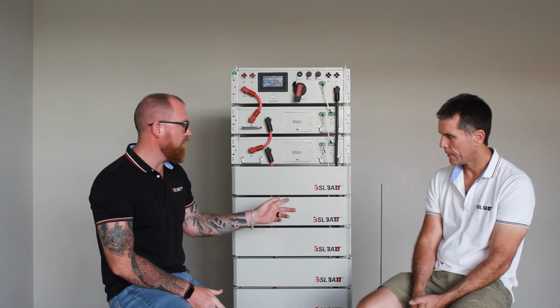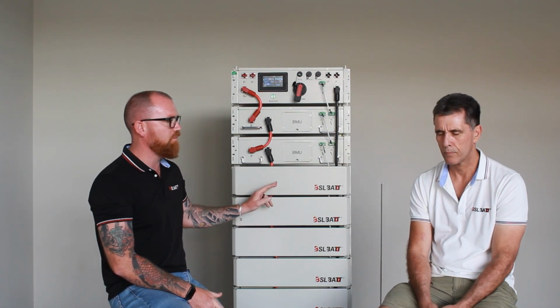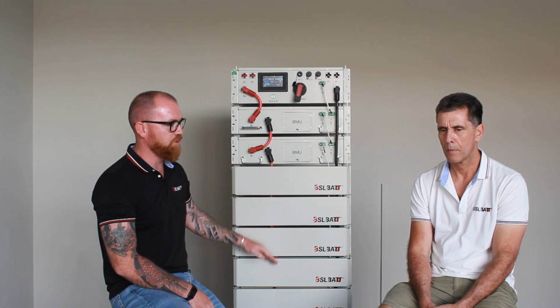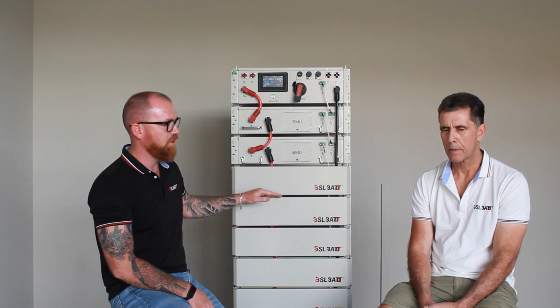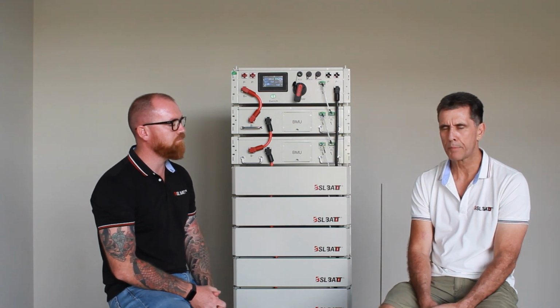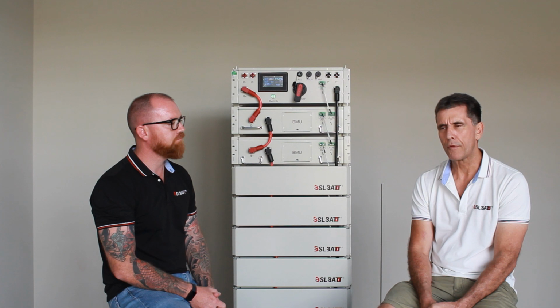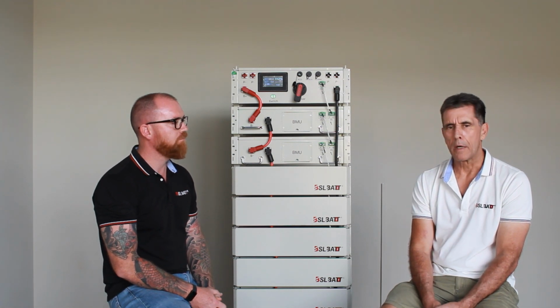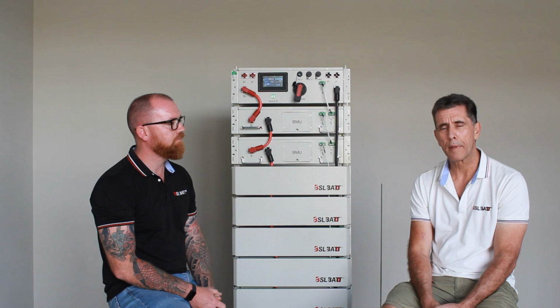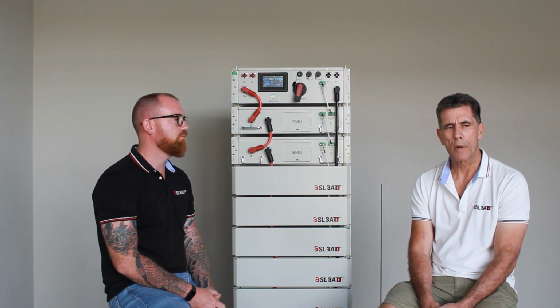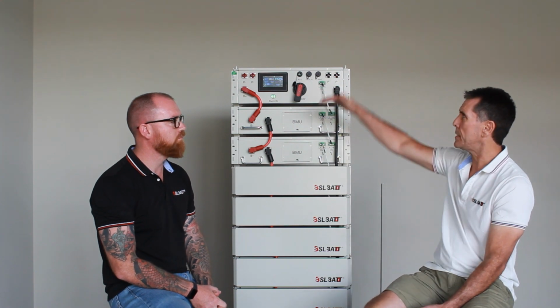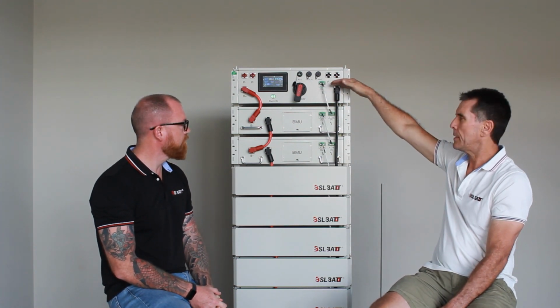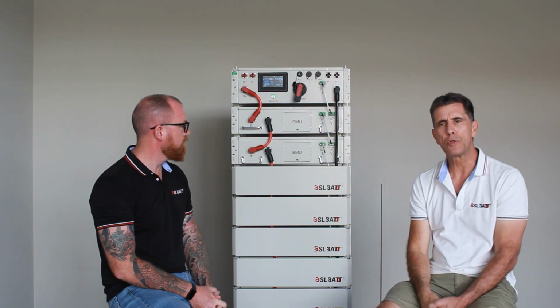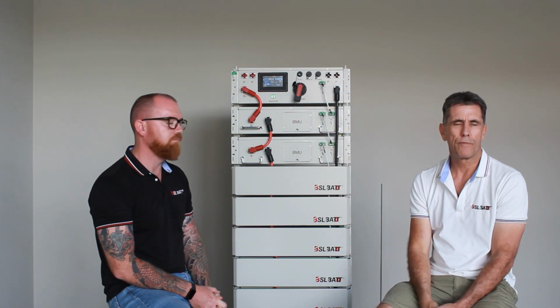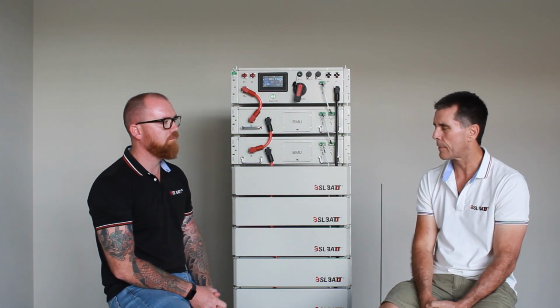In terms of this battery, we mentioned in our first video that it's a 7.7 kilowatt module, each module, with built-in fire suppression - about 7.8, just shy of 7.8 kilowatt hours per block. Nominal volt of about 58 volts, if I remember correctly. There are 18 cells in the block, and then you series them as you require the desired voltage. The BMS is very clever - the BCU unit on top determines the pack voltage and also how many cells there are. There's quite a clever learning algorithm in terms of finding out what size the battery is and adapting to the correct voltage and pack.